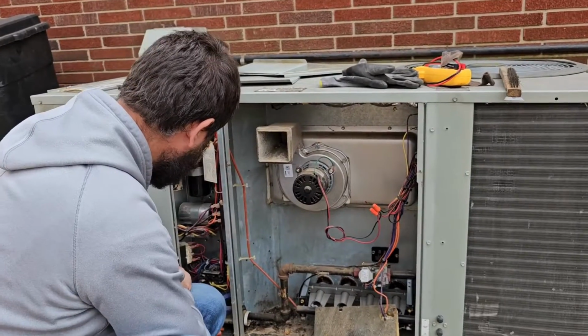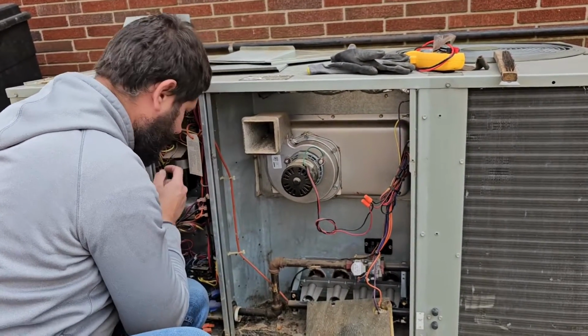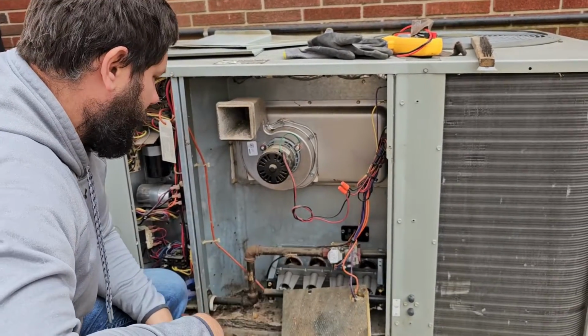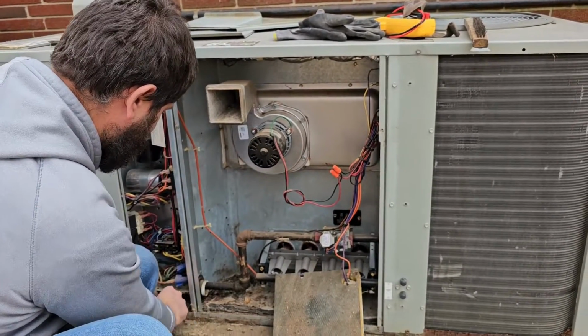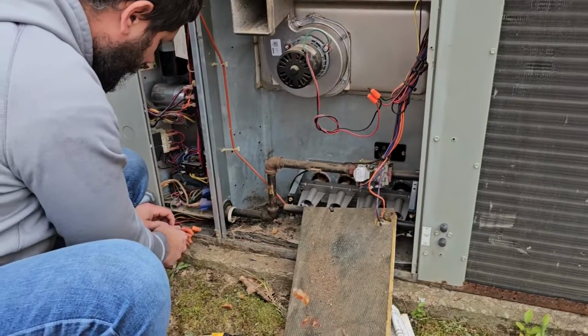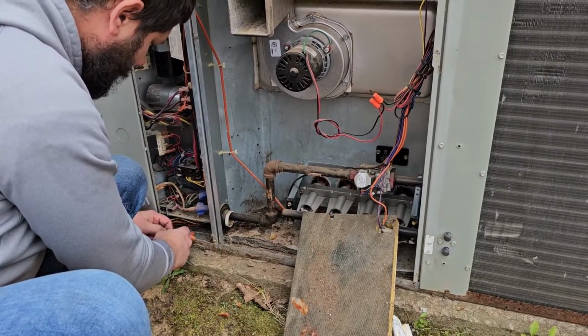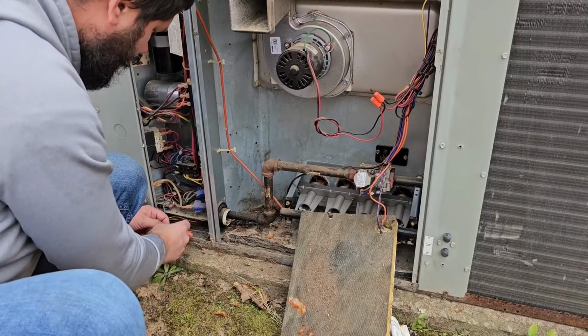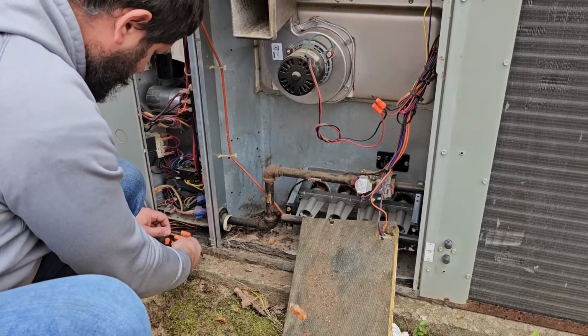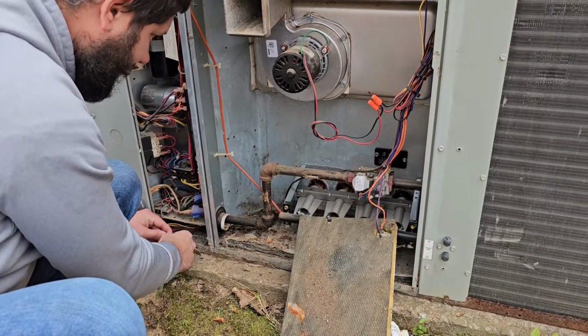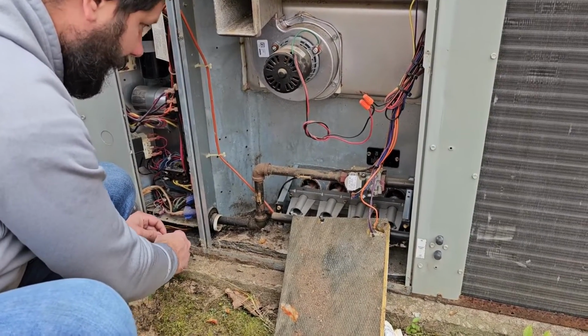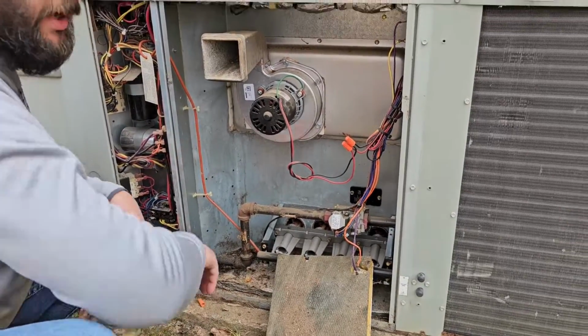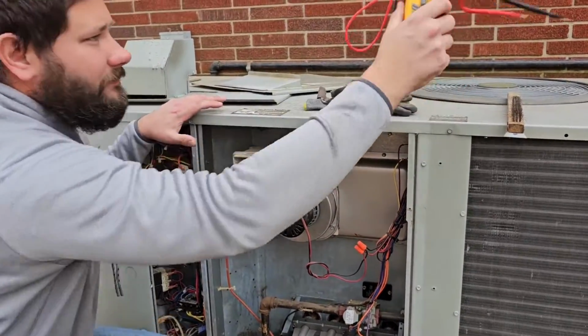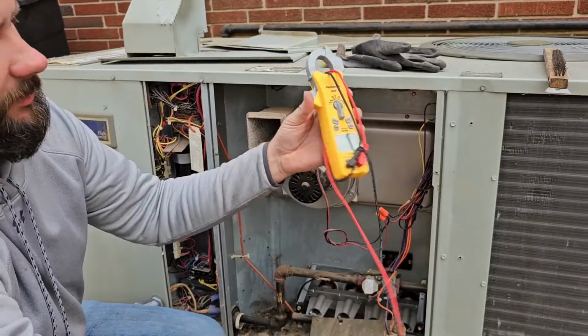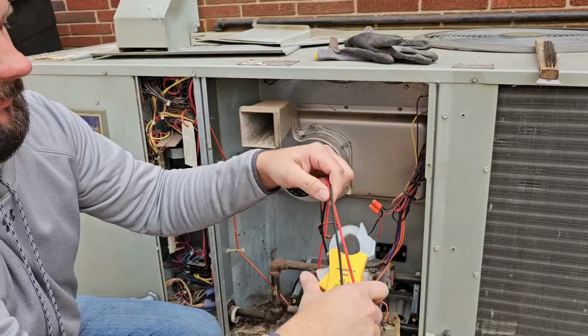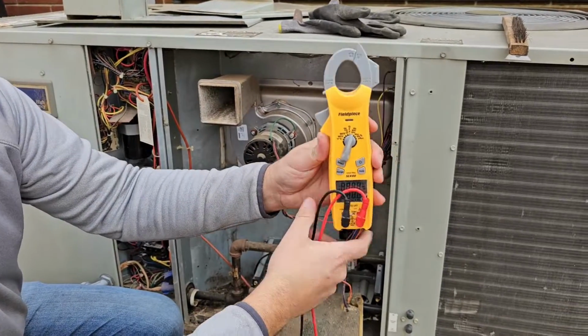Here's our board, and looks like we got a defrost board right here because of course this is a heat pump. So let's go ahead and touch our red to our W1, which is right here, because we want to test everything out. When you go to check a heat exchanger, you want to actually make sure everything's working. I'm going to show you how to check across the limit switch and the pressure switch. So what do you want to do? Set it to volts AC.